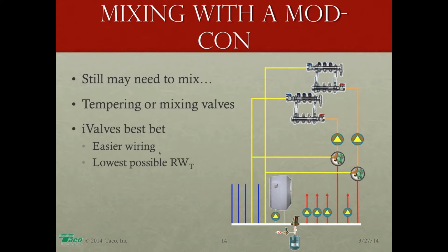The benefit to this is when each radiant runs, we're sending back cooler and cooler water than the boiler would get otherwise, so the boiler is going to condense even more and behave more efficiently. So you get the lowest possible return water temperatures in those situations. So again, there's a lot to like about using the low water temperature capabilities of a ModCon and designing around one low water temperature. But there may be instances where you may be able to employ some mixing with outdoor reset using an iValve from Taco that will add to the overall efficiency of the system.